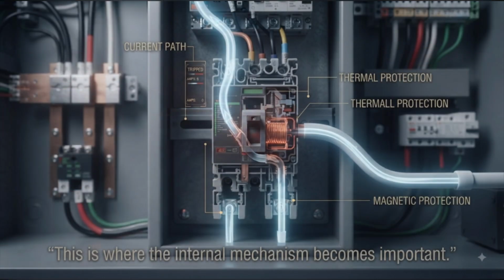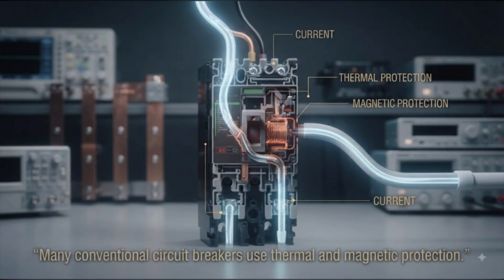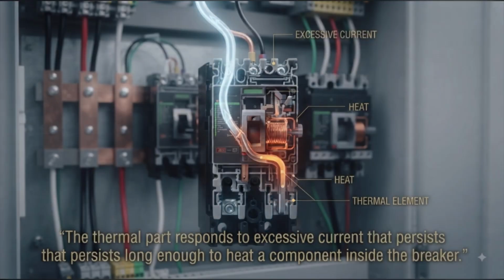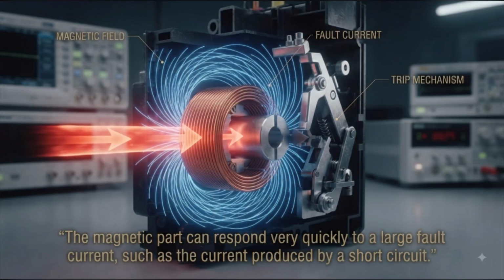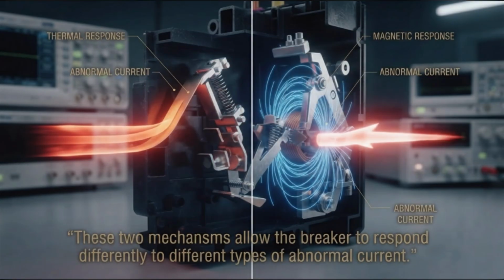How does the breaker detect excessive current? This is where the internal mechanism becomes important. Many conventional circuit breakers use thermal and magnetic protection. The thermal part responds to excessive current that persists long enough to heat a component inside the breaker. The magnetic part can respond very quickly to a large fault current, such as the current produced by a short circuit. These two mechanisms allow the breaker to respond differently to different types of abnormal current.